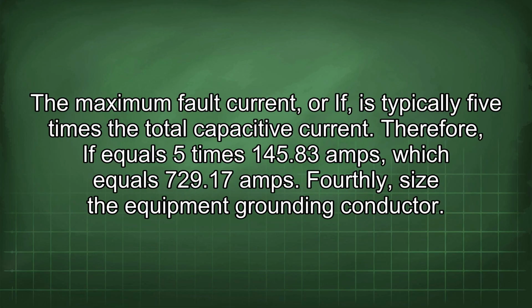The maximum fault current, or If, is typically 5 times the total capacitive current. Therefore, If equals 5 times 145.83 amps, which equals 729.17 amps. Fourthly, size the equipment grounding conductor.